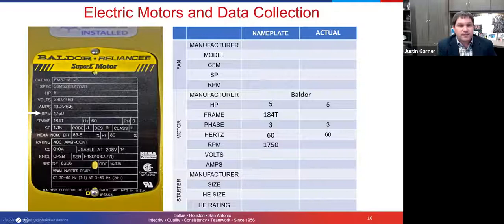In this particular case, this is a 1750 RPM motor. We see RPMs that range much lower than this, all the way up to 3600 RPM, depending upon the number of poles in the motor. In this particular case, we're on a 460 volt system. You see that this motor could operate on a 230 volt system as well. So again, it's important to understand, as we talked about at the beginning of this presentation, the power distribution within the facility and what the expected voltage is for this particular system and this motor. And then obviously, you have to know that voltage because it's going to determine the amperage. If we were at 230 volts feeding this motor, we would have a nameplate rated amperage of 13.2 amps. But because we're using a 460 volt system here, our rated amperage is 6.6 amps.